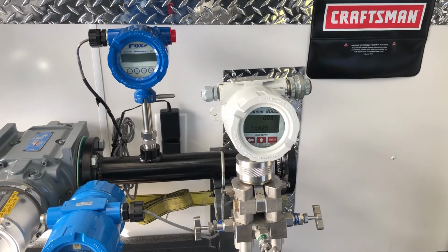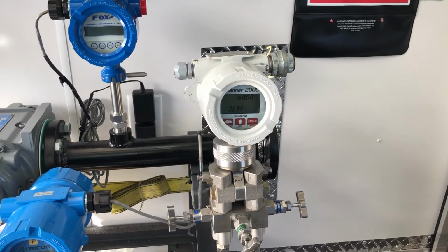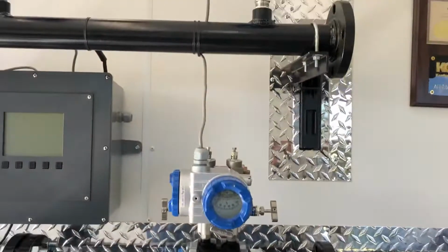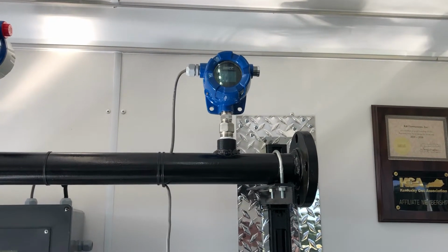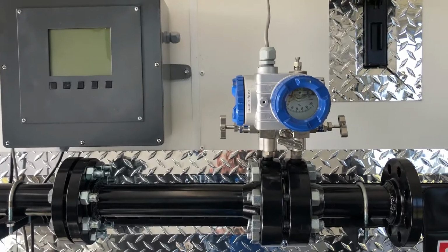compressed air applications. So it's critical to add a pressure transmitter, because for every 1 pound of pressure swing, you have 1% inaccuracy. And for every 10 degrees of temperature swing, you have 2% inaccuracy. So it's critical to infer the mass flow instead of just doing velocity.